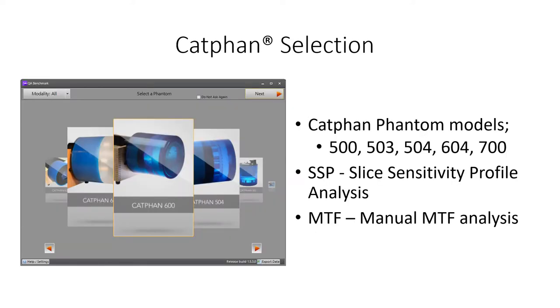The main application screen for AutoQA Plus displays all the CatPhan models supported along with selection options for SSP, slice sensitivity profile, and a standalone MTF measurement function. The user selects a phantom and clicks next to advance. The screen can be disabled on startup, but if needed, can be accessed using the back button at the next screen.